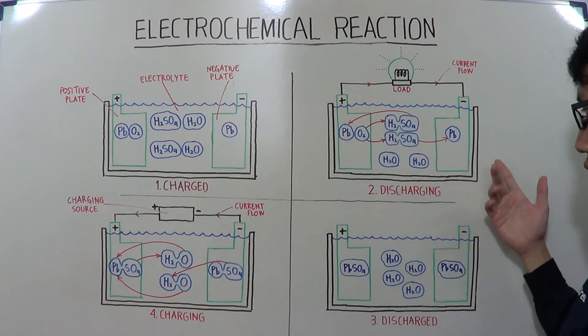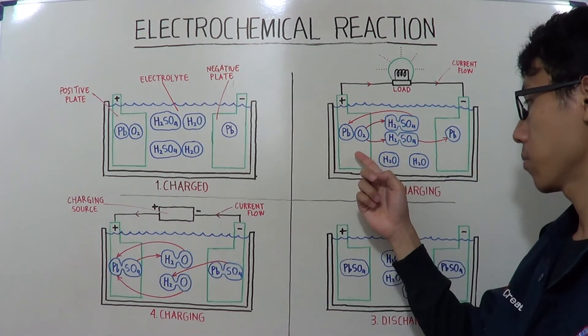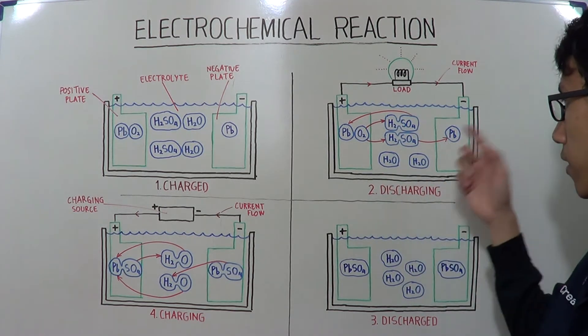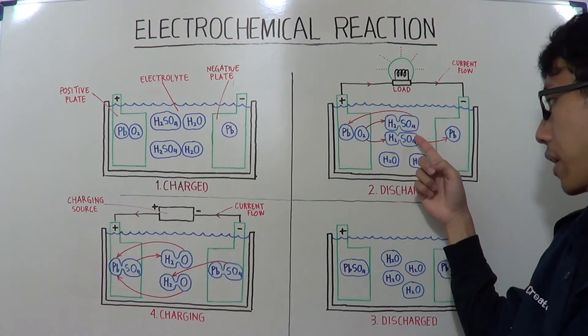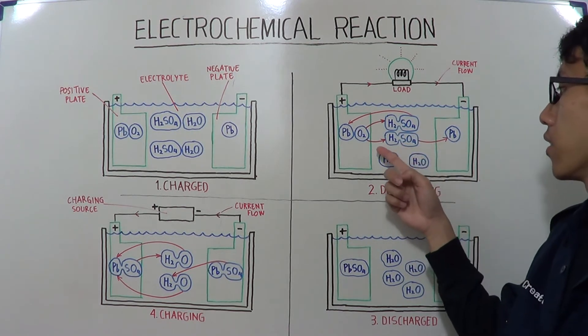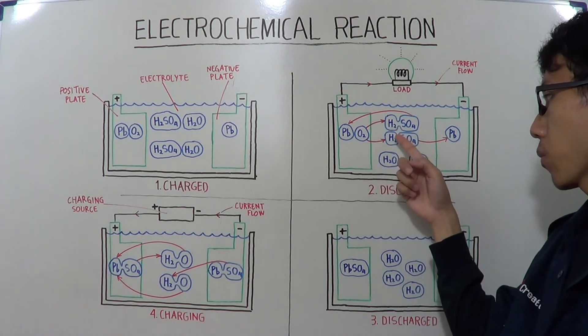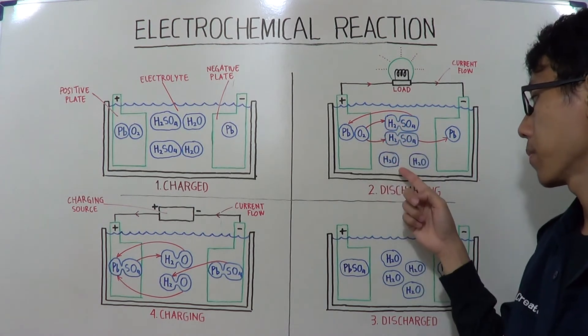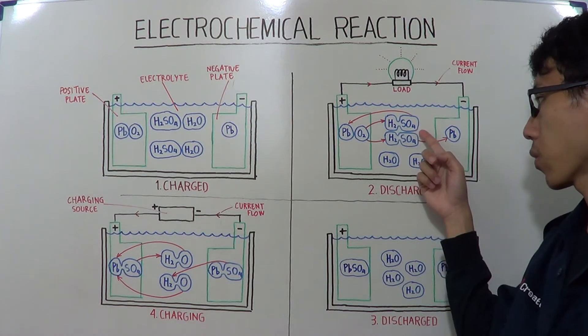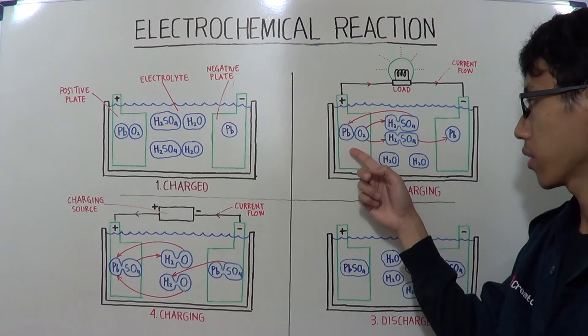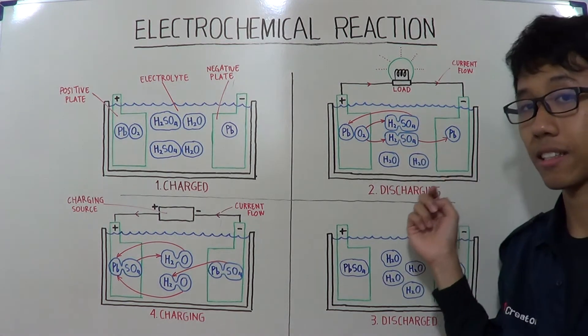As the battery is discharging, the electrolyte becomes diluted and the plates become sulfated. The electrolyte divides into hydrogen or H2 and sulfate or SO4. And the oxygen from the positive plate combines with the hydrogen to form water or H2O. And the sulfate or SO4 combines with lead or PB on both positive and negative plates. That's the second stage.